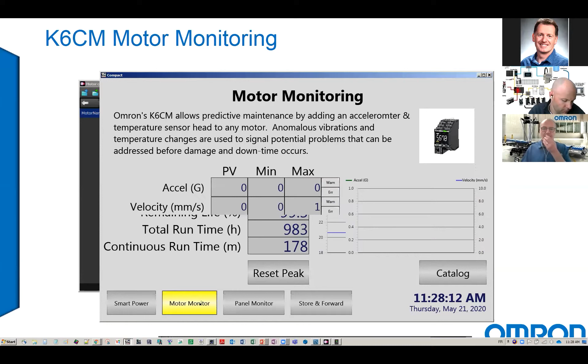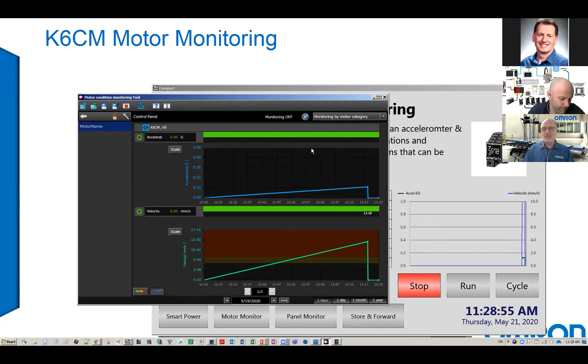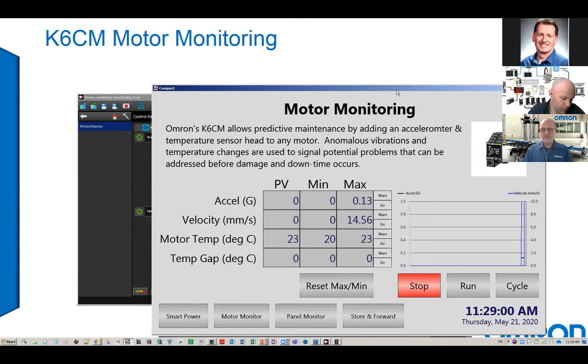If I run the motor, you can probably hear it from my microphone. Now I do have some vibration and velocity being shown on this display here, as well as on this graph. And it will give you the percentage of acceleration and the velocity of your vibration directly on the graph, telling you that you may have some issues with your actual motor at this point in time. And this information is logged with the file here on your PC if you're using the Windows-based application, or you can monitor and report that into your controller with your SQL connection if there's an SQL on your PLC.